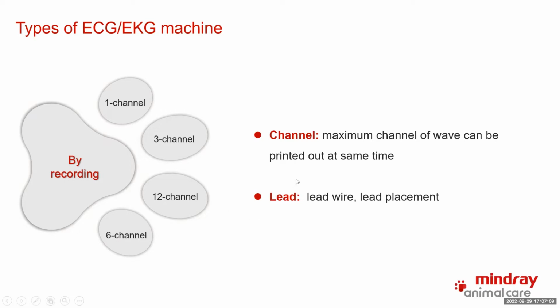As you may know, the lead means the electrode, the number of electrodes you put on the patient's surface. So all these ECG machines are introduced with the 12-lead system. That means they will have a maximum of 10 electrodes placed on the patient side. But normally we only use 4 or 5, and that's enough. For these 3-channel or 12-channel ECG machines, the lead placement is the same, but the channel is different.